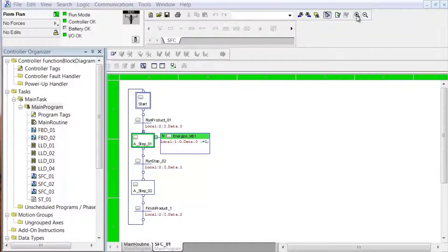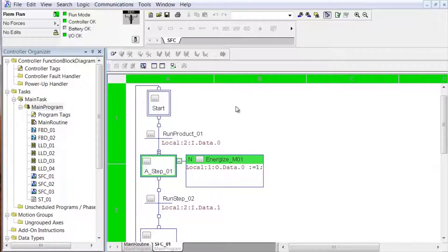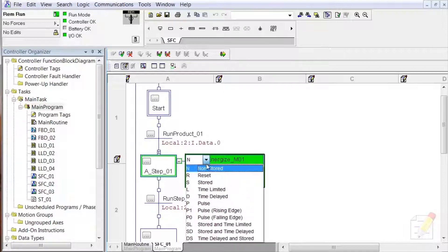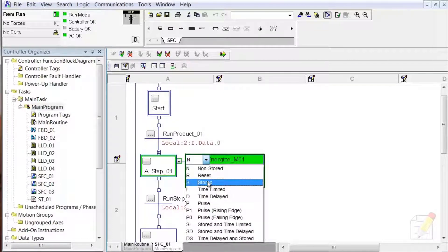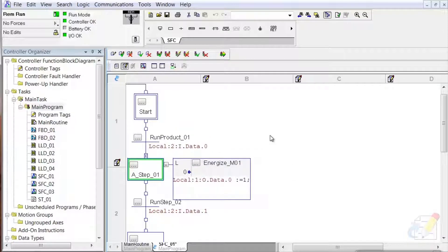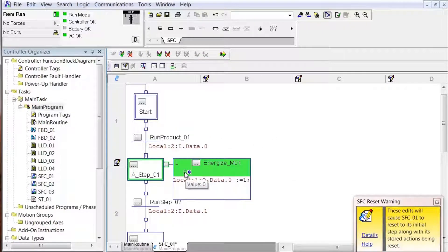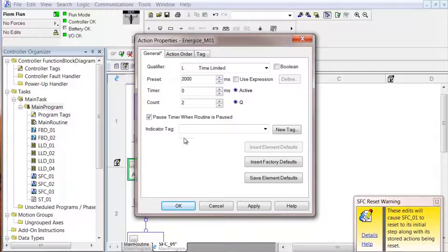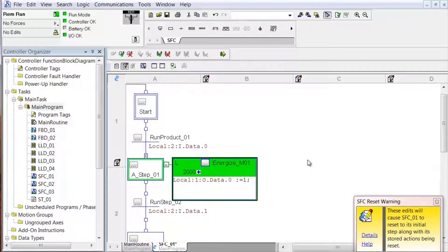We're going to enlarge this a little bit and then put it in the edit mode — remember the pencil and paper. Now we're going to drop down the list and pick L, which is time limited. Click anywhere off of it and we've changed it to time limited. However, we did not put in a value for the time. We can put in a preset here — I had you put in two seconds, or 2000 milliseconds. This is in milliseconds. Now we're going to finalize all edits.